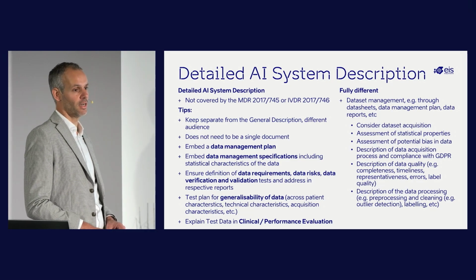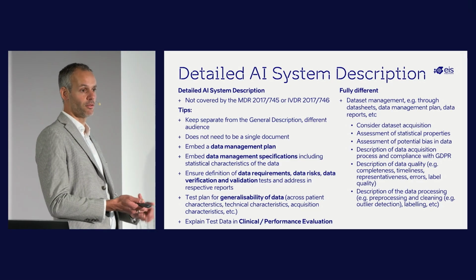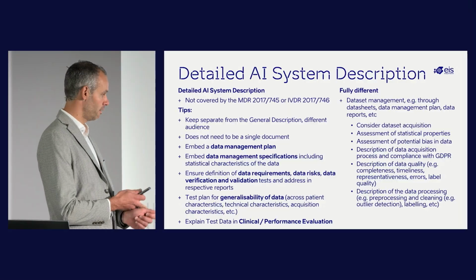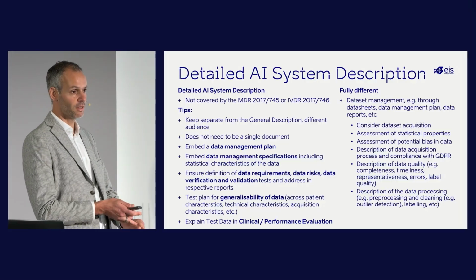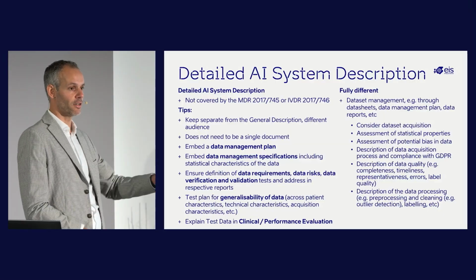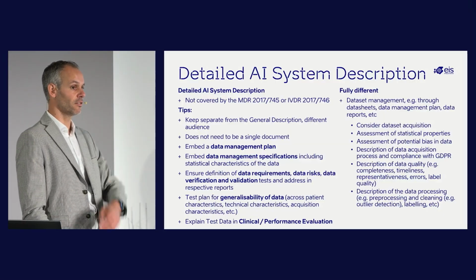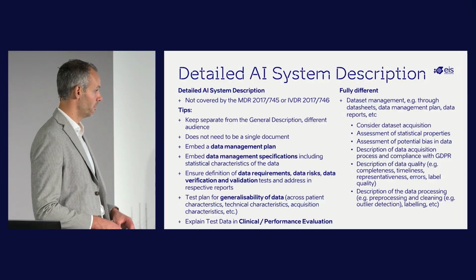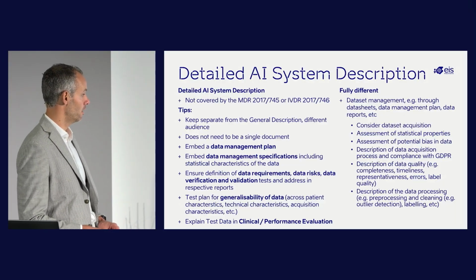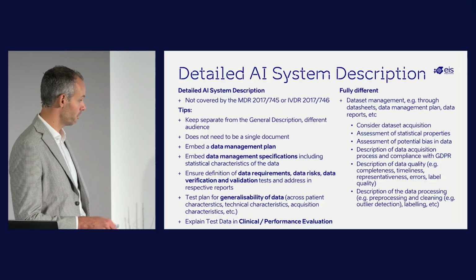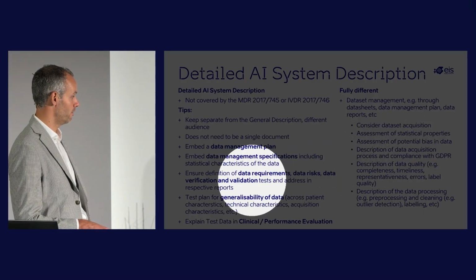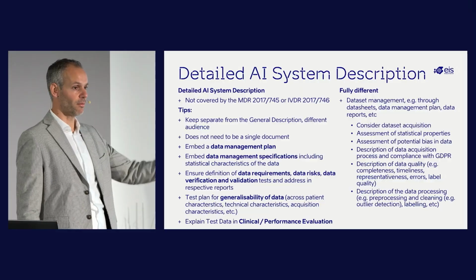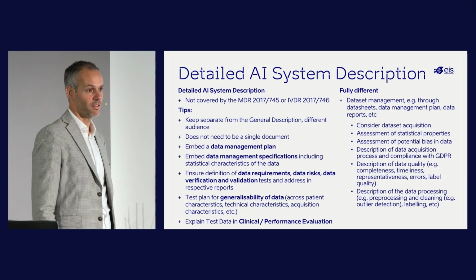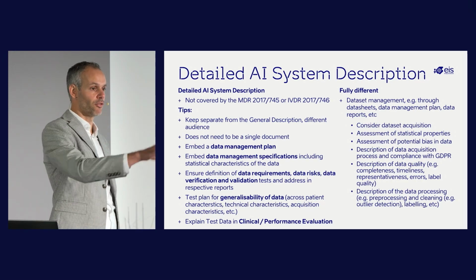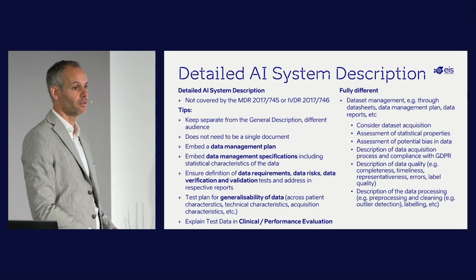And what they do is they allow you to document the requirements, link requirements to tests, and link the requirements also to risks, so that you can clearly see the whole cycle from a requirement to a risk to a test case, and from a mitigation as well back to the test cases. And those systems will also demand, for example, that you define requirements. Just make a separate category on data requirements, have a separate category on data risks, etc. And then on the front end of those systems, you can pull all those risks to create a report.